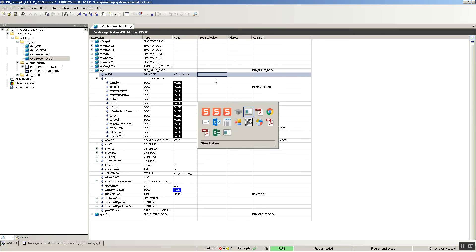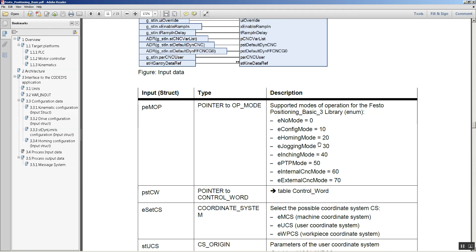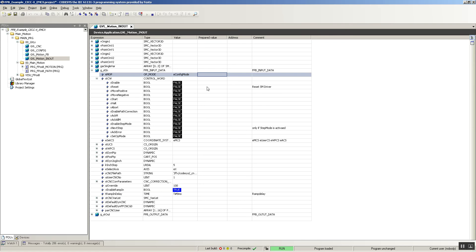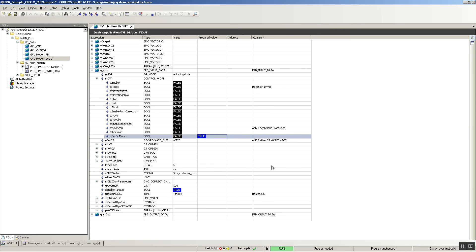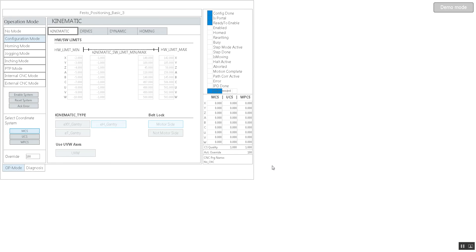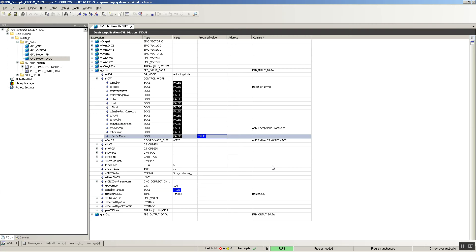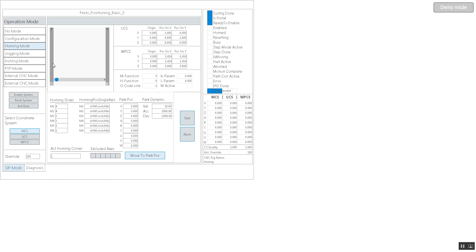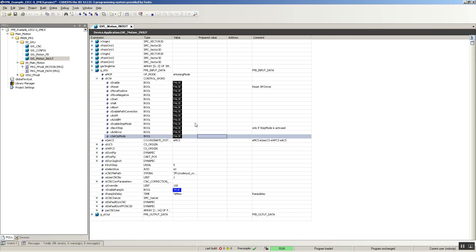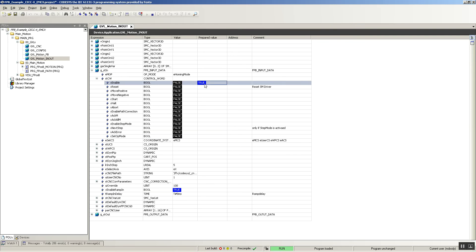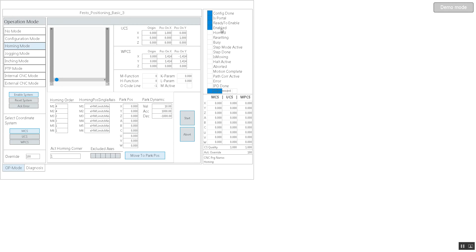Now I'm going to switch to the homing mode by selecting 20, by sending a 20 on the EMOP variable. I set a 20 there, write the value, and then remember to set this bit to true, because otherwise it's going to stay in configuration mode. I set that bit to true, then false, and then I'm on homing mode. Now I want to enable the system. I enable the system here, write the bit — it should be enabled. It says the drives are enabled.